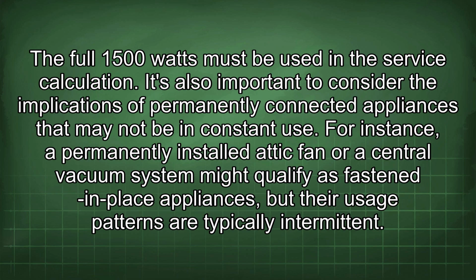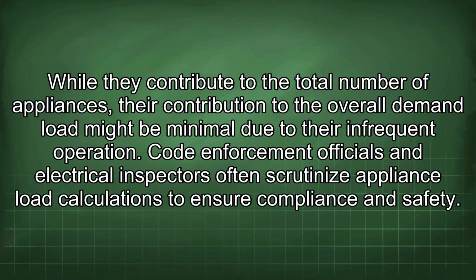It's also important to consider the implications of permanently connected appliances that may not be in constant use. For instance, a permanently installed attic fan or a central vacuum system might qualify as fastened-in-place appliances, but their usage patterns are typically intermittent. While they contribute to the total number of appliances, their contribution to the overall demand load might be minimal due to their infrequent operation.